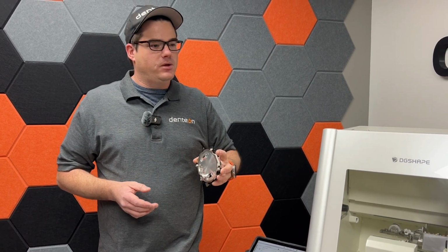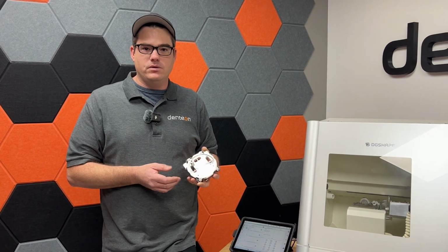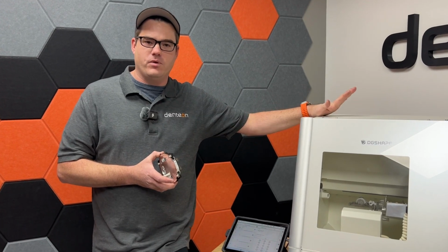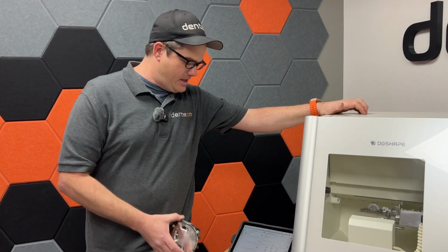And then thirdly, if you've taken the machine apart or serviced it, again, it's been disturbed, calibrate it. And lastly, if the machine has gotten a new firmware update, you also must calibrate it. So those are the only 4 times we calibrate. There's no recommended regular interval. Doing it daily, that is redundant, and you're frankly asking for trouble. Doing it weekly, also redundant. The calibration is a tool, and it should be reactive to those 4 points that I already outlined. So let's get into how to do the calibration for those of you guys that are unaware.